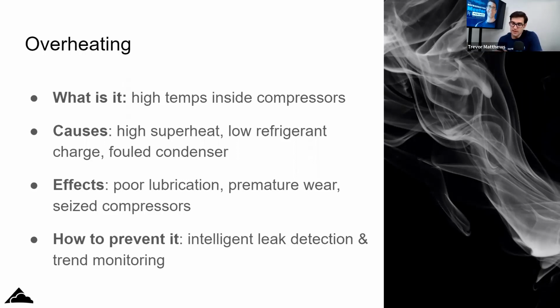And when you start looking at performance charts, I had a training last night talking with a bunch of refrigeration professionals, you need to understand the performance chart of that compressor. And when you start running high compression ratio, more heat of compression, more work on the compressor, you start to heat up more, your oil starts to get less viscous, it gets thinner, so your pump out rates go higher, and then it leads to a bunch of problems. And this all can be done through analytics if you want.